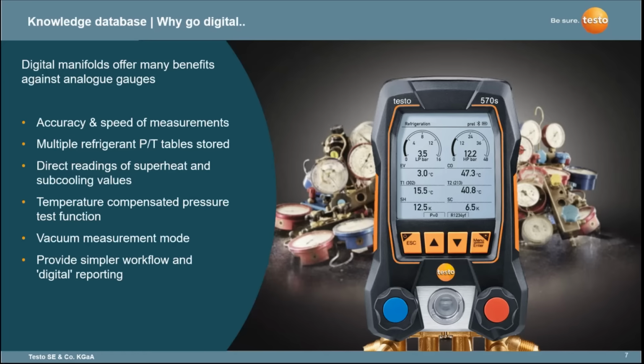So, for example, you've got within the devices a temperature compensated pressure test function. So when you're using your nitrogen pressure test on a system to strength test it, you can switch this device into a test mode for the pressure test, and it will very clearly show you your start pressure, end pressure, and length of run of the pressure test.